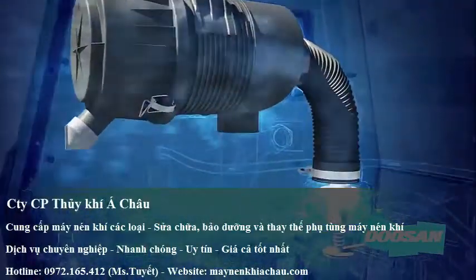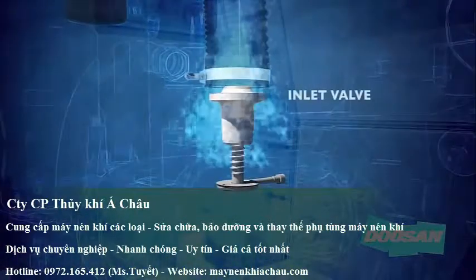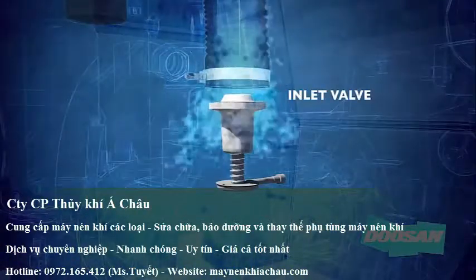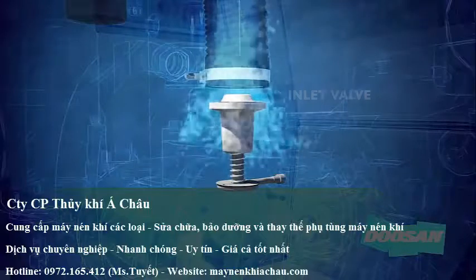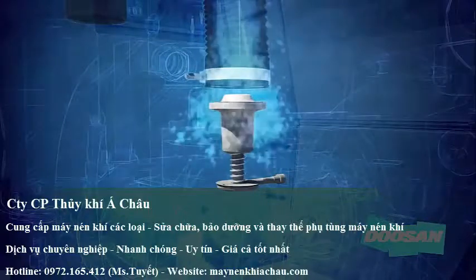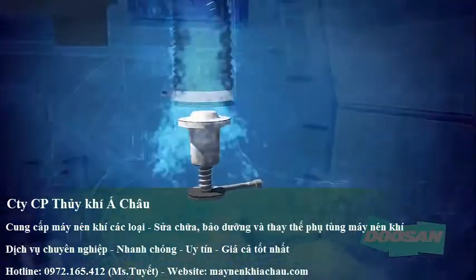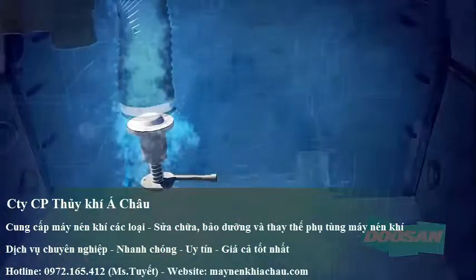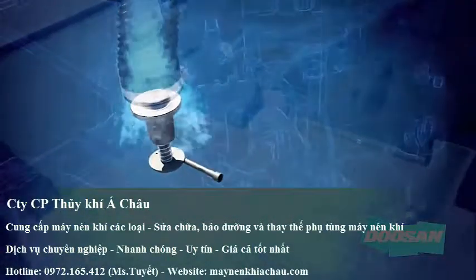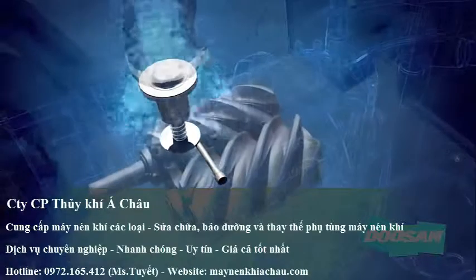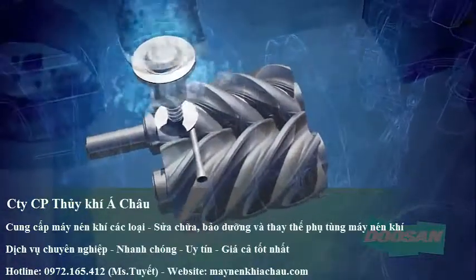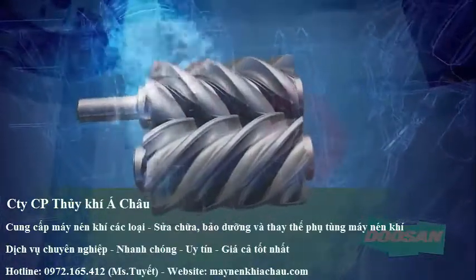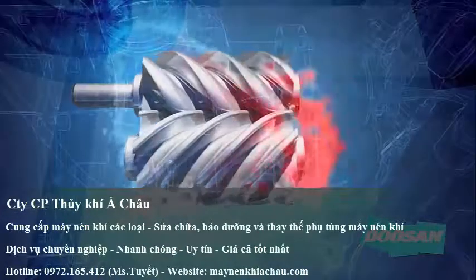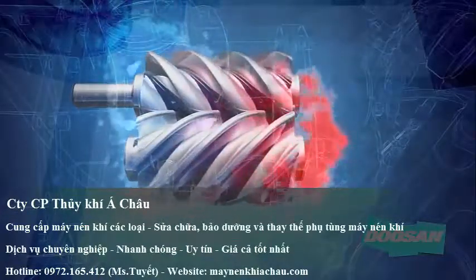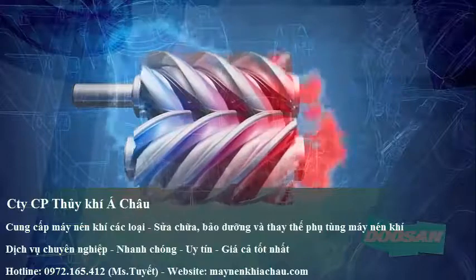Filtered air continues through sealed piping to an inlet valve that controls the volume of air reaching the air end and prevents oil from reversing towards filters after shutdown. Next, air enters the air end, which is a fixed displacement pump that uses two helical rotors to compress air. As the rotor screws turn, they form a partial vacuum which sucks air into the helical rotors. The amount of air that fills the air end is measured in cubic feet or meters per minute.